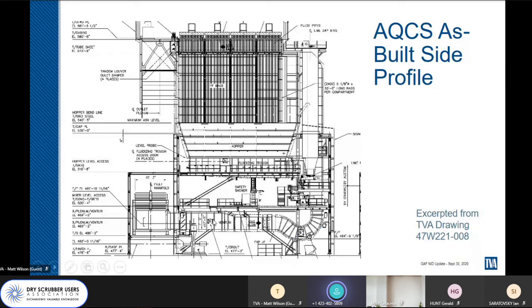We've got to remember, this is still warm, hot flue gas coming through here. It's had no water or moisture added to it. So it's still 300 degrees plus. Of course, the byproduct coming down is more on the order of 200 degrees Fahrenheit. Yes, there have been some problems with the grit screw conveyor, but I believe in general, this works pretty good. Whenever we go in here, or the plant inspectors go in here, there is some product here. But in general, we do not have any bridging issues, do not have any bad problems removing the dropout.